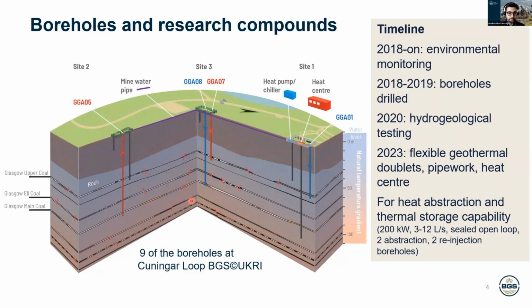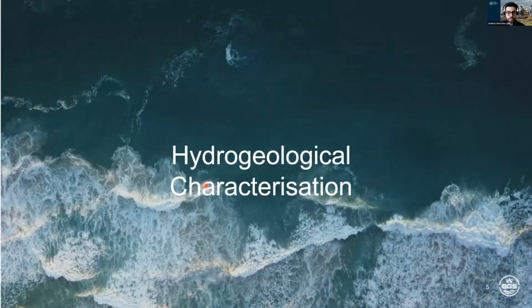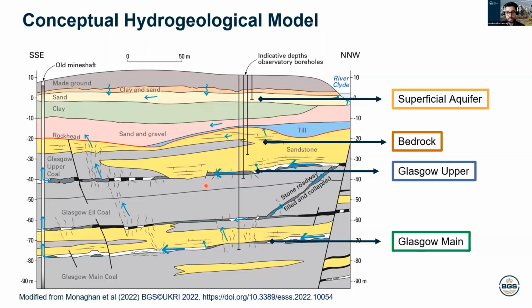Two of the boreholes are ready for water abstraction, one in the Glasgow main and one in the Glasgow upper, with flow rates between 3 and 12 liters per second. This is all connected to a heat center with a heat pump and chiller of 200 kilowatts. There is the possibility for reinjection both in the Glasgow upper and in the Glasgow main, so we can use different combinations of abstraction and reinjection, in the same coal seam or at different levels. I'll now show some of the initial hydrogeological characterization results from this environmental monitoring.